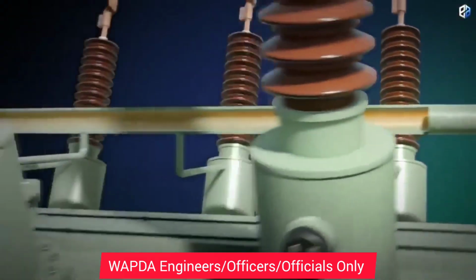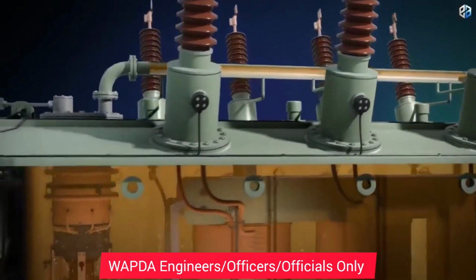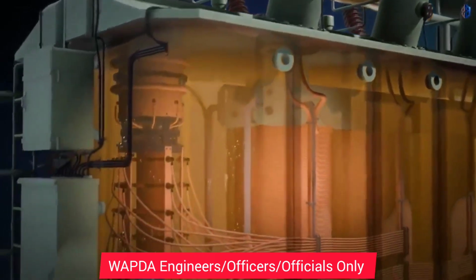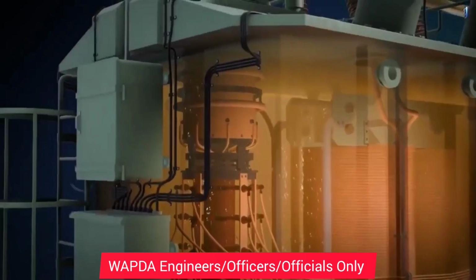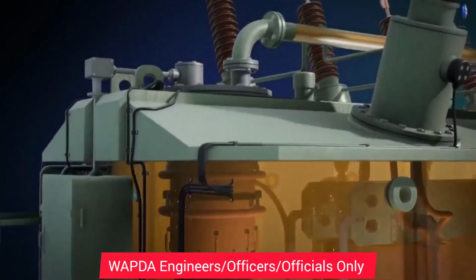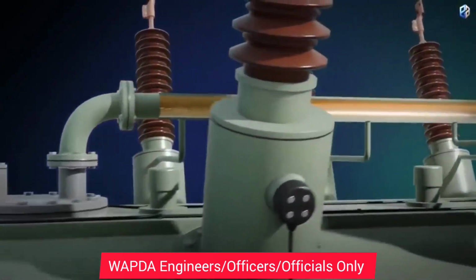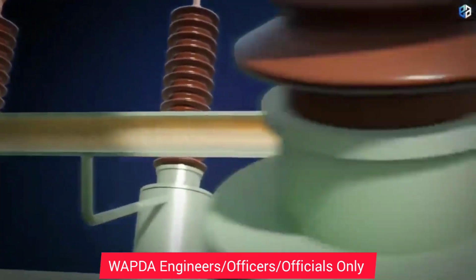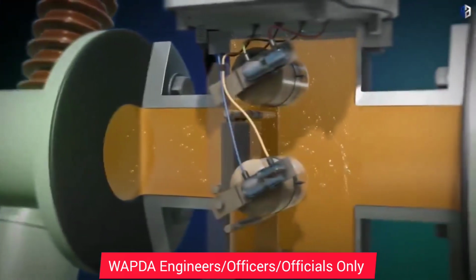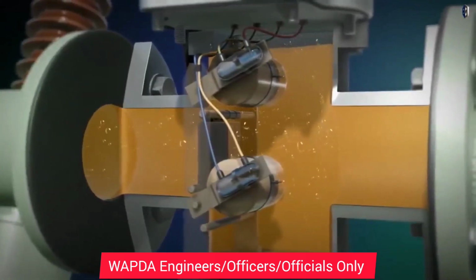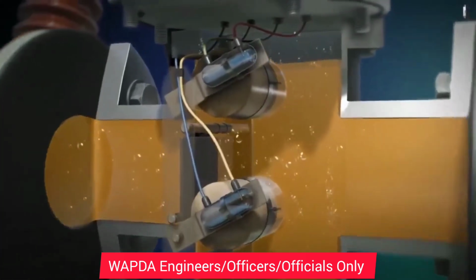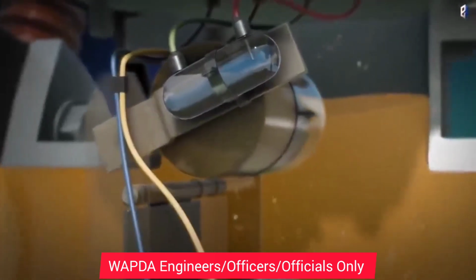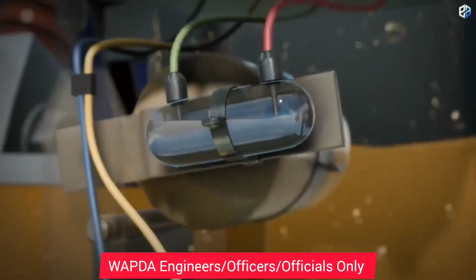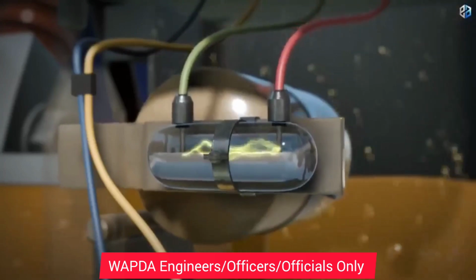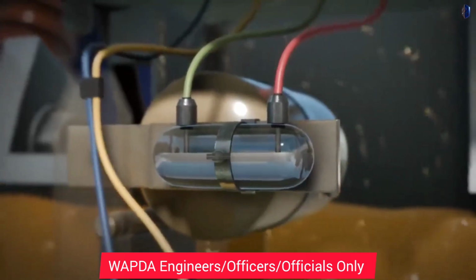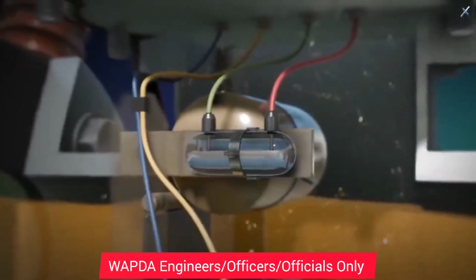What happens if a fault occurs inside the transformer, for example a partial discharge, or if the transformer is overloaded? This produces gases that are lighter than oil. These gases rise in the direction of the Buchholz relay and displace the insulating liquid, that is the oil inside the relay, and collect at the top. If the amount of gas rises above a certain and previously defined level, the upper float lowers and a contact is closed. This is the first warning signal, an indication of a possible internal fault. As a rule, a warning message is sent to the operator of the system.